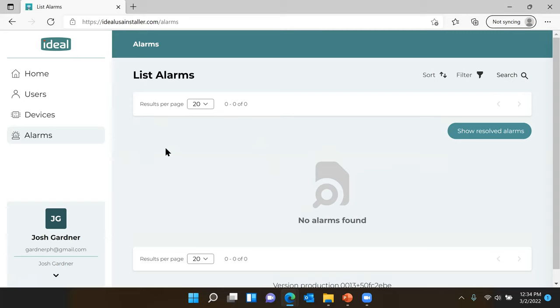So the way I explain it is most homeowners are trying to get this notification if they're away, if something goes down. In our thermostats, our Nests, which are horrible, Ecobees, Honeywells, all those, you basically set a low temp or a high temp alarm. So if the house drops below 55 degrees, you get an email notification. Well, if your house drops below that, the piping in the walls could be much colder and you're running the risk of freezing. With this, we can get an alert as soon as that boiler goes down. So essentially, you could get a notification before the house even drops a degree or two, and we know that boiler went down.